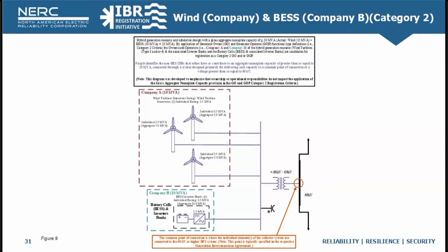Again, the common point of connection is identified by the orange circle and is at a voltage of 69 kV, which exceeds the 60 kV threshold. Therefore, identified in purple are the facilities that meet the Category 2 criteria, and as a result, the owner of Company A, the wind generation resource, and the owner of Company B, the battery energy storage generation resource, are candidates for registration as a Category 2 GO, and the operator is a candidate for registration as a Category 2 GOP.